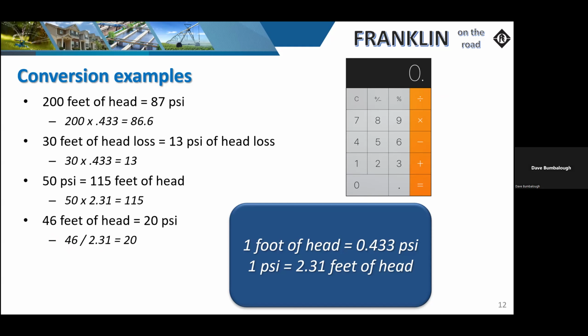sizing a pump. We typically will lead off with feet of head. So we're lifting that water from a distance in the well up to the surface, and then from the surface, maybe an elevation change, plus or minus. Plus, we usually have to satisfy some kind of pressure device that's telling the system when to turn on and turn off. So that's where we're going to convert that PSI. Okay, so as we go through here, I'll have another exercise. We'll go over that, convert that, and keep it all in one form or the other.